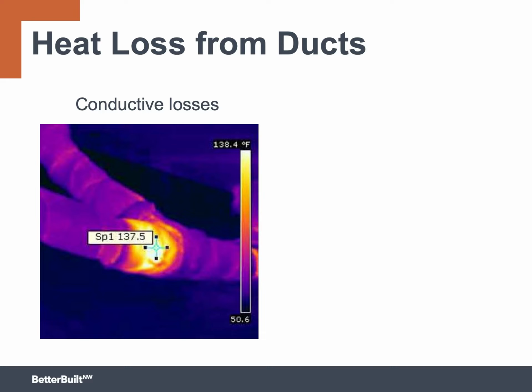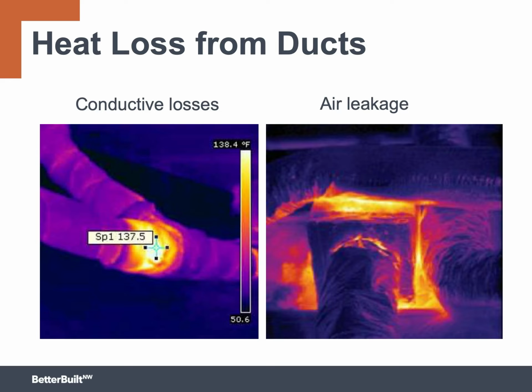On the left, you can see an example of conductive losses. This particular yellow spot on the image on the left is actually a Y connection, a metal Y, and it's not insulated, so it gets a lot of heat loss. So it kind of exaggerates the effect a little bit, but you can certainly see the ducts standing out from the background on the infrared image on the left. Metal fittings that connect sections of flex duct can cause big problems. And on the right, you can see how air leakage affects heat loss. That's a distribution box with a lot of air leaking around through seams and little gaps that haven't been sealed.